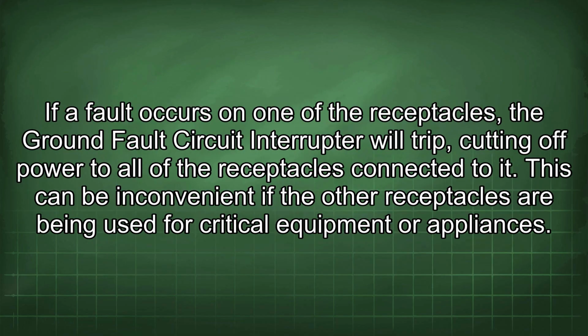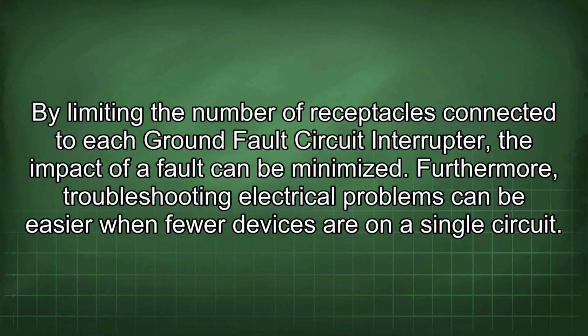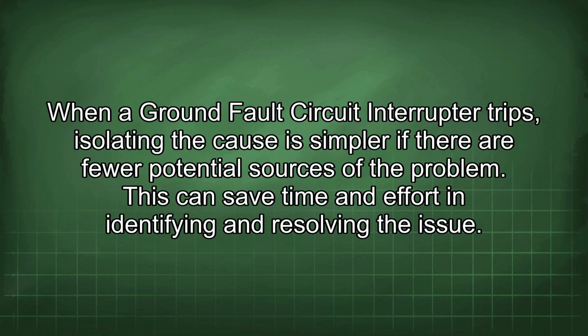If a fault occurs on one of the receptacles, the ground fault circuit interrupter will trip, cutting off power to all of the receptacles connected to it. This can be inconvenient if the other receptacles are being used for critical equipment or appliances. By limiting the number of receptacles connected to each ground fault circuit interrupter, the impact of a fault can be minimized. Furthermore, troubleshooting electrical problems can be easier when fewer devices are on a single circuit. When a ground fault circuit interrupter trips, isolating the cause is simpler if there are fewer potential sources of the problem. This can save time and effort in identifying and resolving the issue.